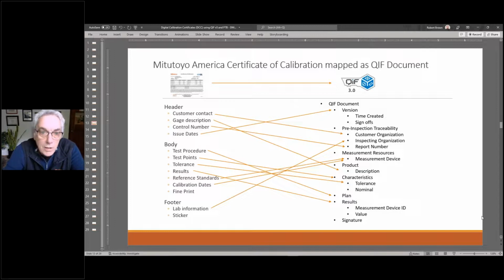In our certificate, we've got a header section with customer contact, gauge description, control number, issue dates. We've got a body, which is the test procedure, which also includes the test points, the tolerances for these different test points, the actual or adjusted results, the reference standards that are used, calibration dates, and of course some fine print. And then we've got a footer where we'd have lab information and a sticker that you can affix to the gauge itself with the calibration information.